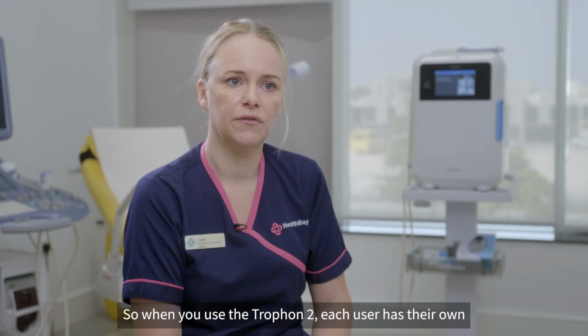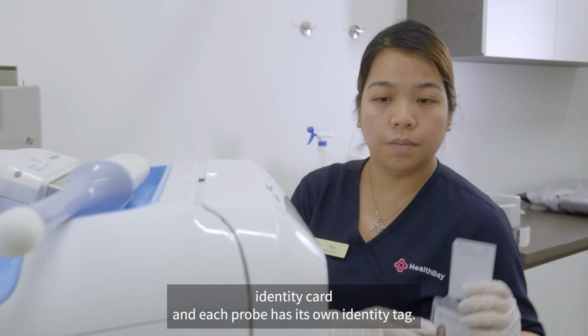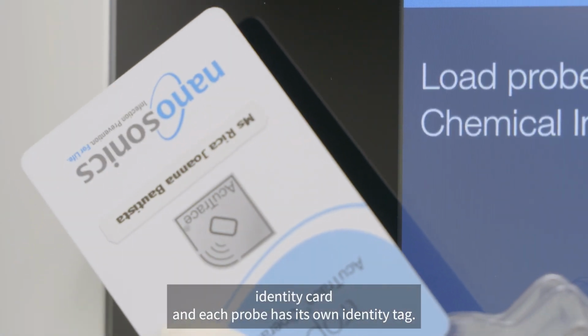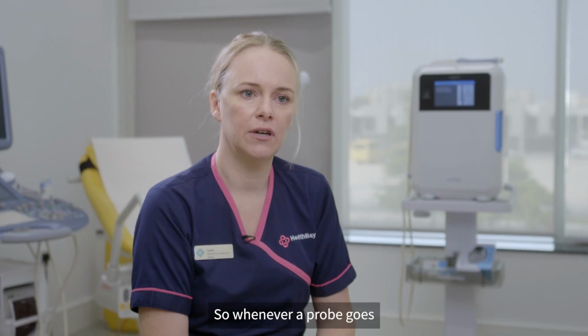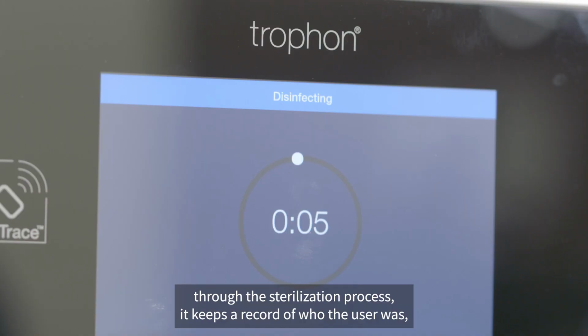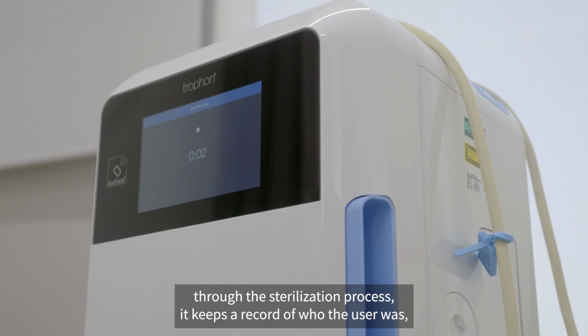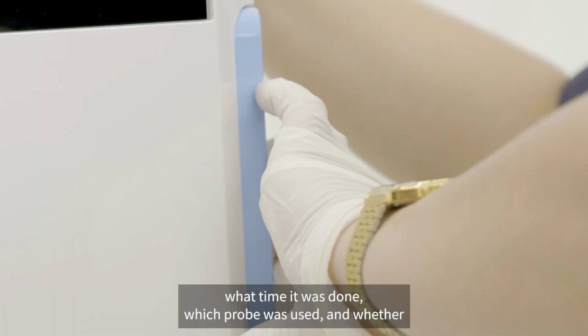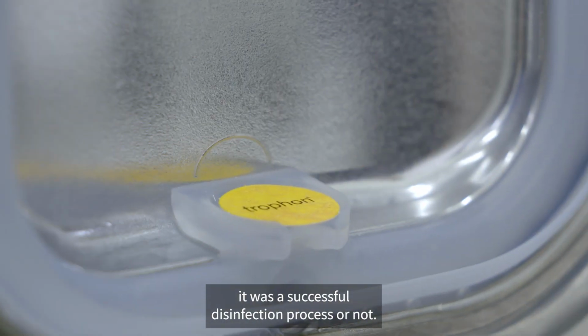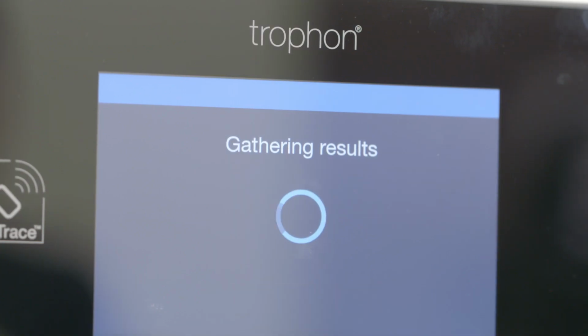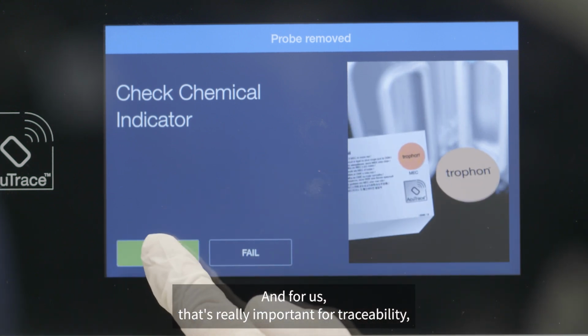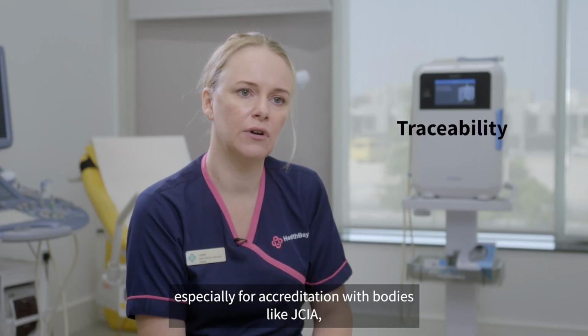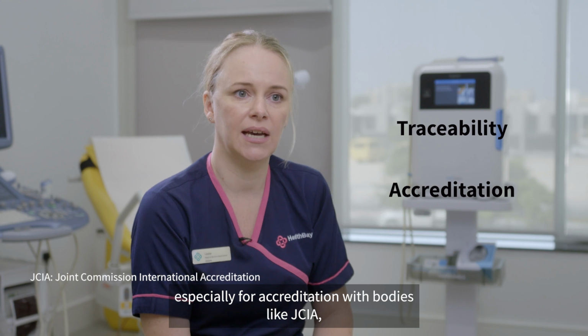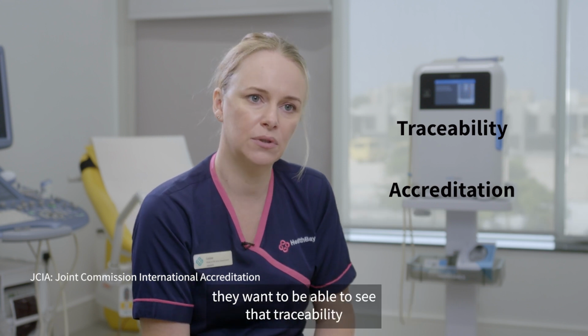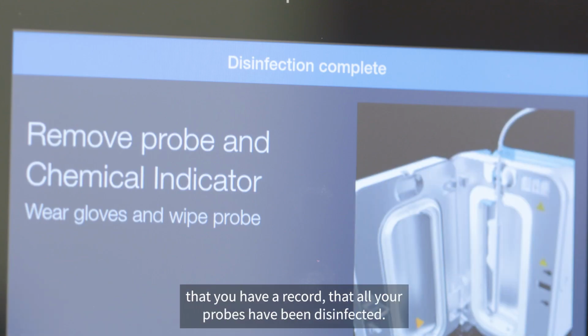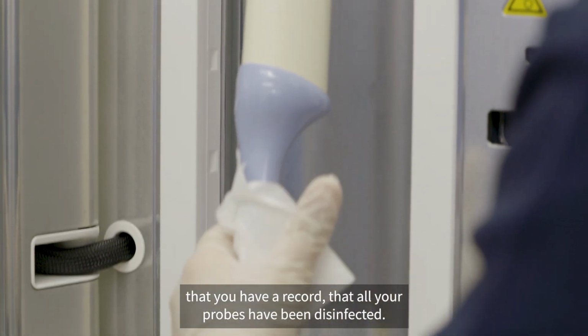So when you use the Trophon 2, each user has their own identity card and each probe has its own identity tag. So whenever a probe goes through the sterilisation process, it keeps a record of who the user was, what time it was done, which probe was used, and whether it was a successful disinfection process or not. And for us that's really important for traceability, especially for accreditation with bodies like JCIA. They want to be able to see that traceability, that you have a record that all your probes have been disinfected.